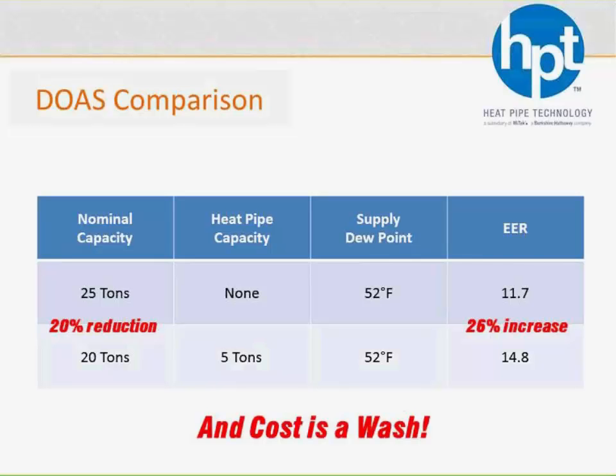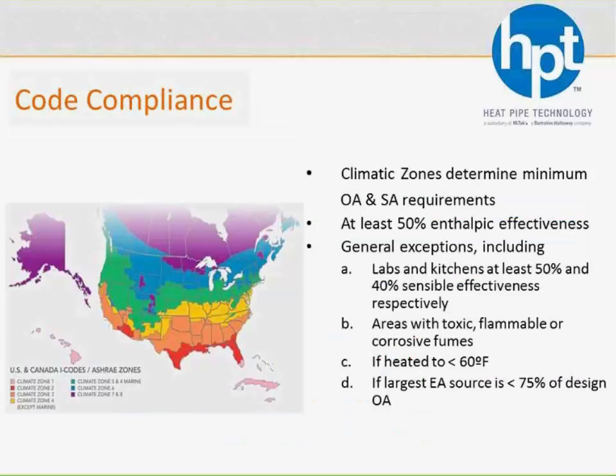So keep in mind that you can get a wraparound heat pipe, and I'm not going to say this is every time. It depends on the project. It depends on the manufacturer, but there's a very good chance that the add for the heat pipe is about the same as the savings for downsizing the equipment. If it's not the same, it's pretty darn close, and you've just made your system about 25% more efficient. Another nice thing is that it's going to meet code.